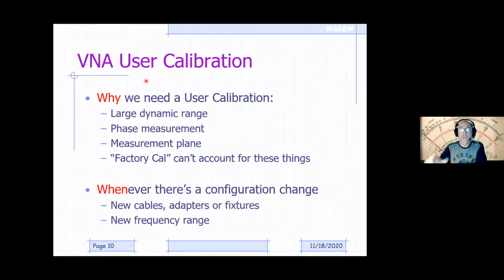But when do we need to do that user cal? Really, it's whenever there's a configuration change. Maybe I'm changing cables, or I'm changing adapters or fixtures for how I'm connecting up to my device. Or more importantly, and probably the most common reason, is when you have a new frequency range that you're measuring over. You set up a frequency range, you do a calibration. You set up a different frequency range to make a measurement. It's ideal to repeat the calibration over that new frequency range.